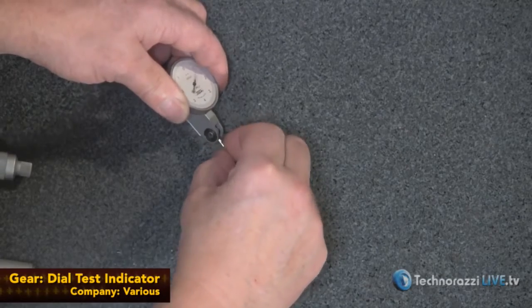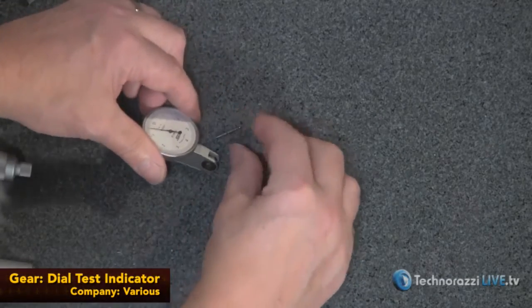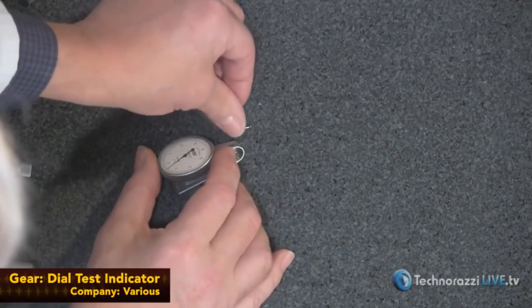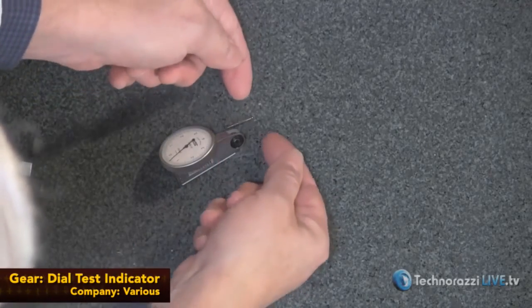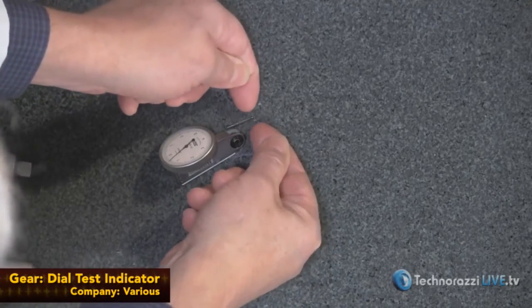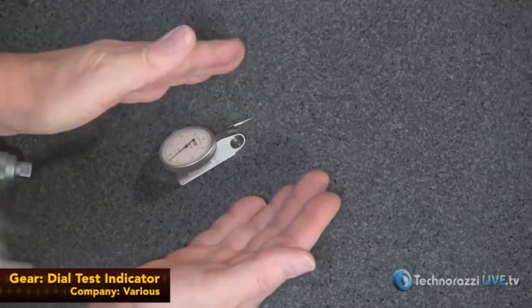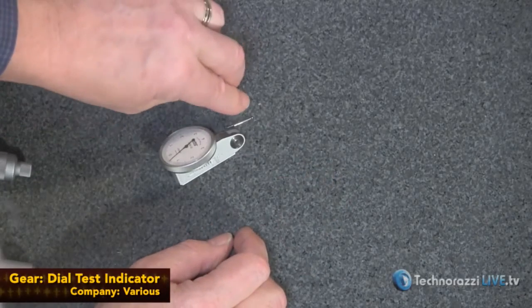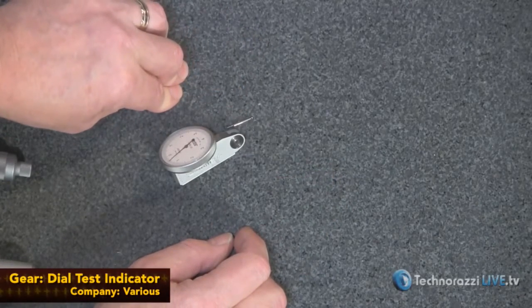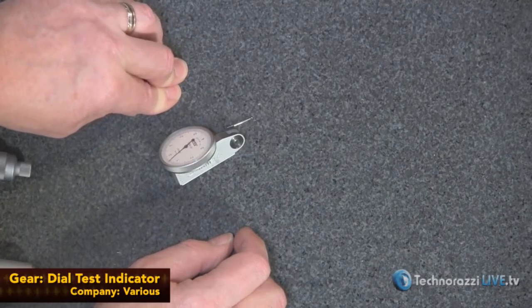Okay. Last thing to consider would be the contact point. The contact point is the most replaced part on these. They wear on the top and the bottom because of how they're used. And bring a magnifier with you. If you look through a magnifier and you see they're worn, that contact point is going to need to be replaced. So maybe factor that into the cost when you're buying it. If the gauge itself seems fine, but it's just a contact point, then you could still be getting a good buy. You just need to replace that.